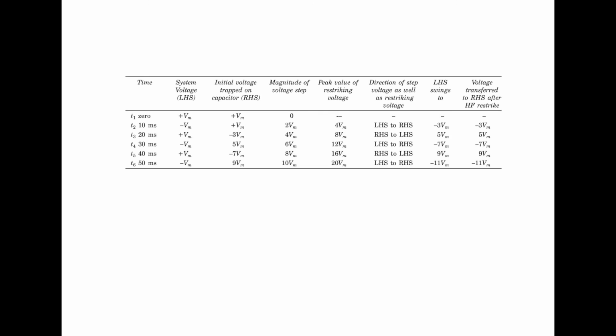In this table, we have the time, system voltage, initial voltage trapped on the capacitor, magnitude of the step voltage, peak value of the restriking voltage, direction of step voltage as well as restriking voltage, what the LHS swings to, and the voltage transferred to the RHS after the high frequency restrike. So this is shown in this table also. This is all about the phenomena associated with the breaking of the circuit: first, current chopping, and second, the voltage buildup during the interruption of capacitive currents. So this is all about this lecture. Thank you very much.